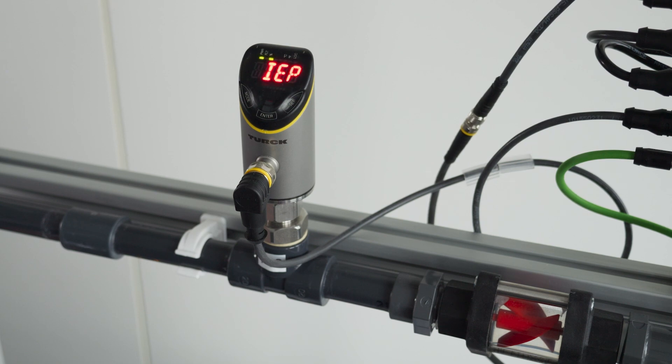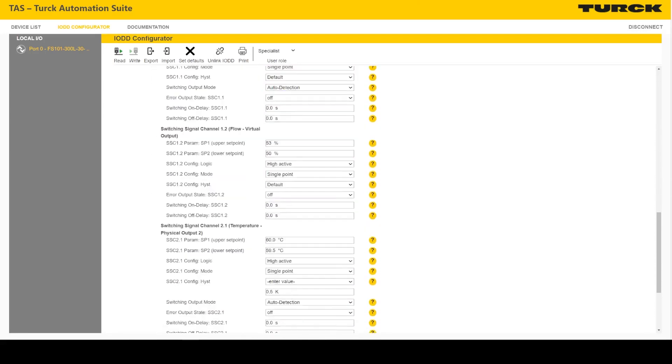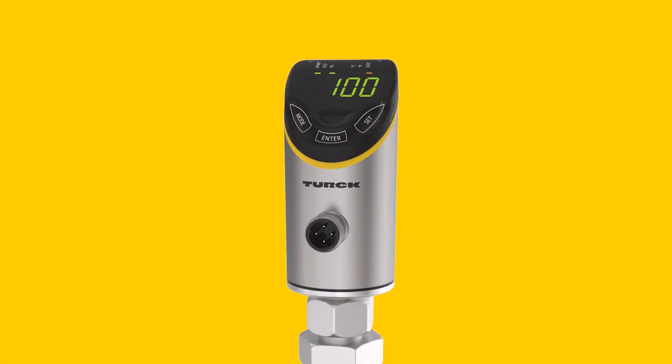You now saw how the FS101, in the same look and feel of the Fluid Plus family, is very easy to operate, and also how the delta flow monitoring actively prevents any incorrect settings on the flow sensor. The settings done here were using the capacitive touch straps on the sensor; settings and parametrization can also be done via IO-Link. The FS101 comes with IO-Link's latest smart sensor profile, and with IO-Link and rated IP67, it can be easily integrated into any decentralized automation solutions offered by Turck — your global automation partner.